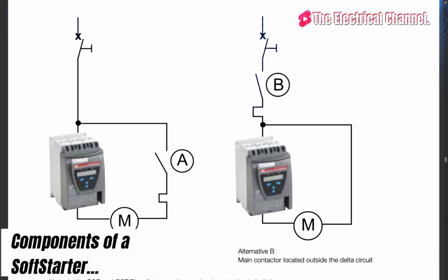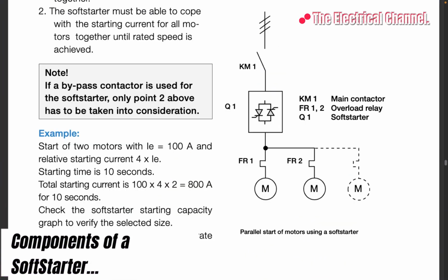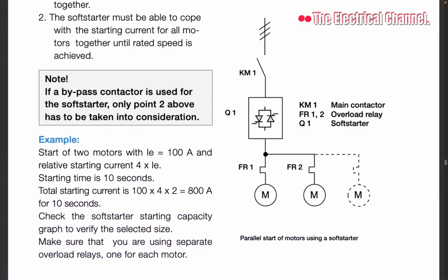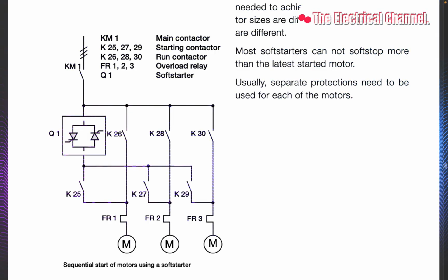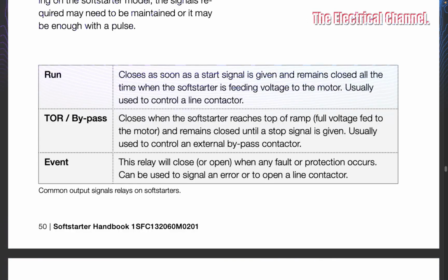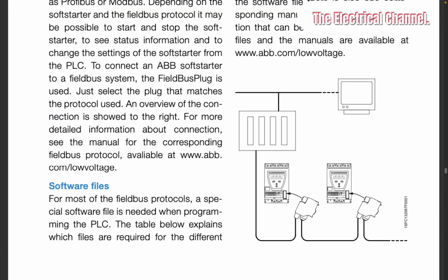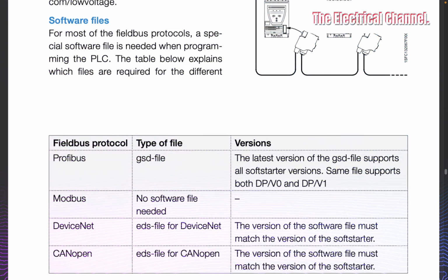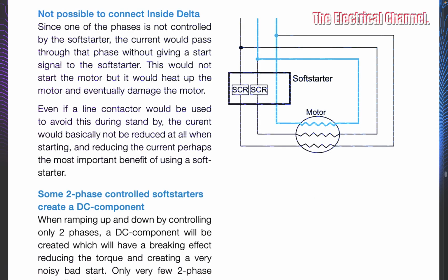A soft starter consists of only a few main components. There are the thyristors that can regulate the voltage to the motor and the printed circuit board assembly, or PCBA, that is used to control the thyristors. In addition to this, there are the heat sink and the fans to dissipate the heat, current transformers to measure the current, and sometimes display and keypad, and then the housing itself.